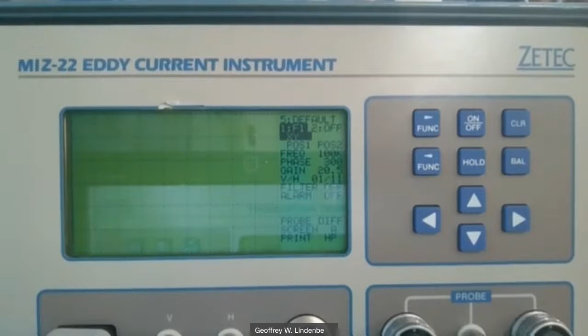To figure out how to set these up, your lab manual has the setup procedure for each probe. In each manual there's a setup procedure for doing surface cracks, and you'll do three different ones: flat surface cracks, a crack in a radius, and a crack in a bolt hole. The setup for those is all basically the same, you set up for the surface crack and tweak it a little for each of the others. The other one you'll do is corrosion, looking at corrosion, and there's a separate setup procedure for doing a corrosion inspection.